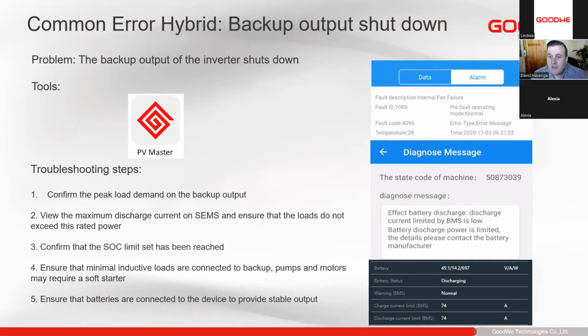So one of the most common errors we have on the backup output is the backup shutdown. For this, we need to confirm the peak load demand on the backup output. As I showed you in the example in SEMS Portal, you can go there to see regularly what the customer's loads are. Very often the customer will have higher loads when the utility is on, and when the utility is off, they are limited by the discharge current. As I mentioned earlier, we always have a look at this discharge current limit.